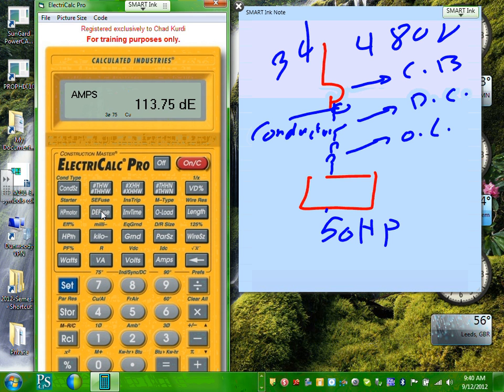That's the fuse size. If you click again, it will tell you what percentage they're calculating at, 175. If you click again, it will tell you which table it went to, 430.52. One more time, and it tells you the fuse size. Then the second click will give you the percentage that they sized there. The third click will give you the NEC code book, and you go back to the fuse size. So 113.75, what's the next standard? 125. If you don't know, where would you go? 240.6. Cool?